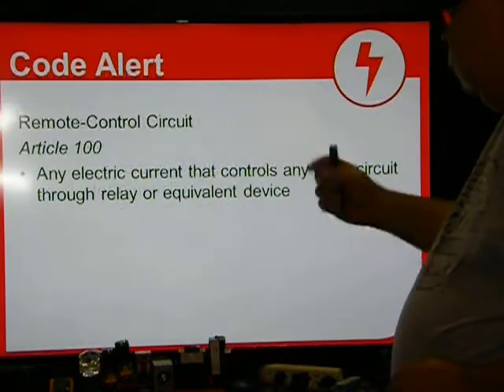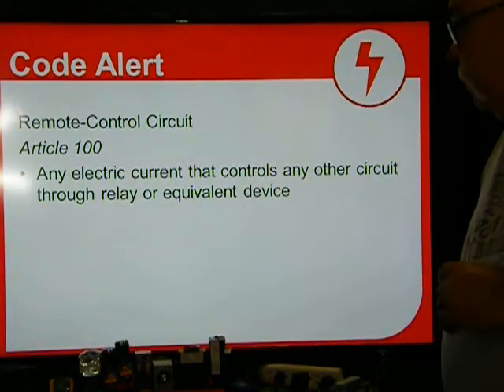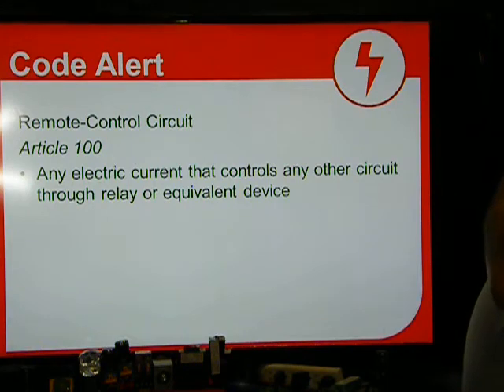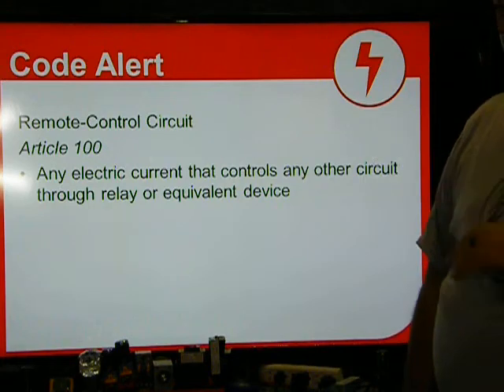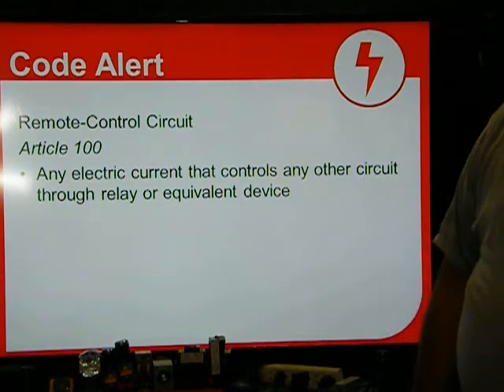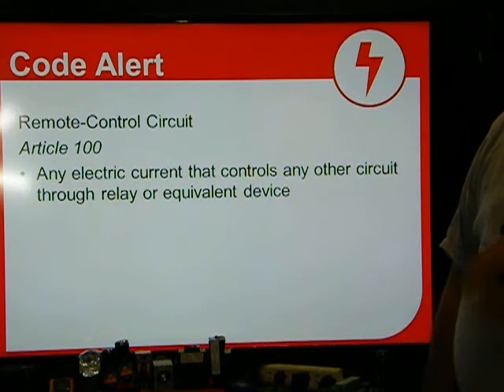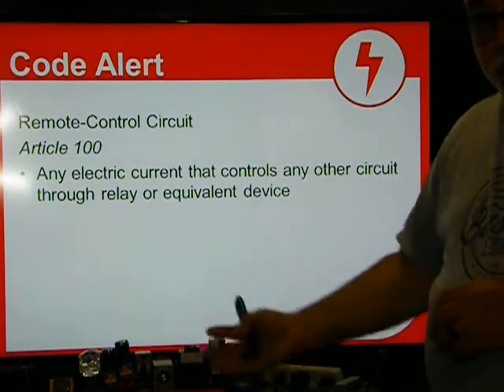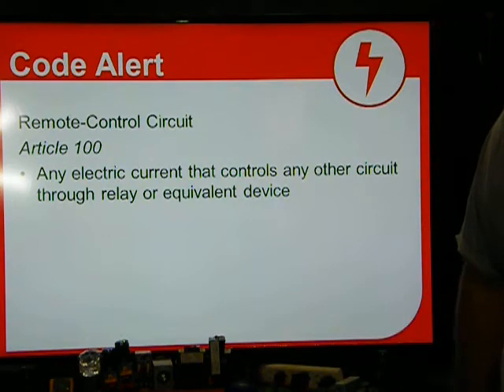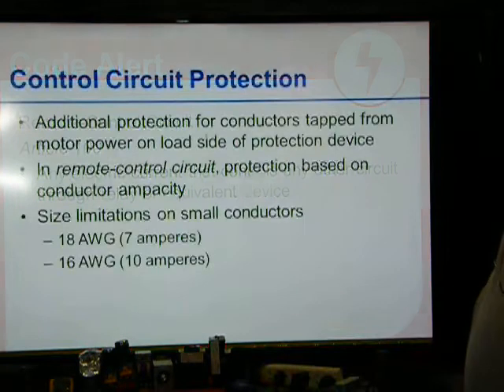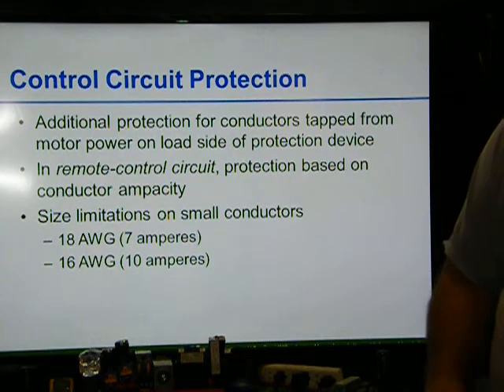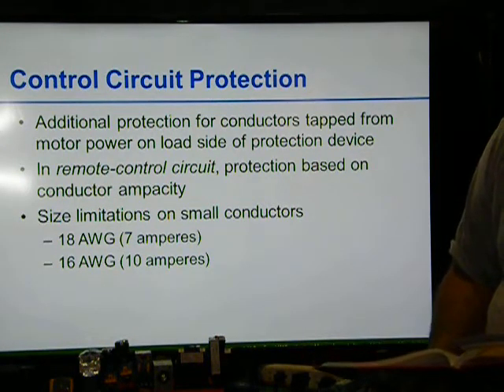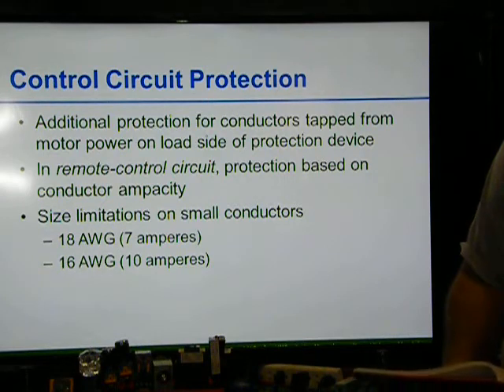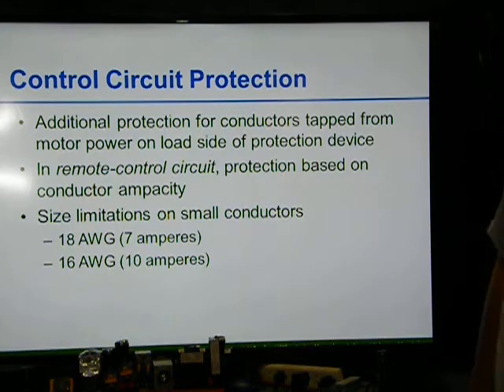Okay, remote control circuit, Article 100: any electrical circuit that controls any other circuit through a relay or equivalent device. So now it's just a circuit that comes in that helps control something. It's carrying small currents, but it's not carrying the current of the actual load, which would be the motor. Motor control connections: the wire diagram is used to show the connections and components of a motor circuit. The wire diagram shows a control circuit.